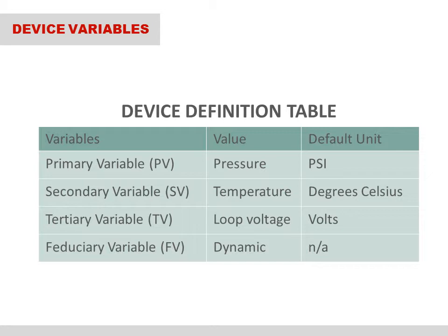The secondary variable, or SV, is the temperature in degrees Celsius. However, this is not the process temperature. This is the temperature of the 815 PT's internal electronic components. Since the 815 is a pressure transmitter, not a temperature transmitter, it is incapable of providing the temperature of the process. The SV is provided via HART. The tertiary variable, or TV, monitors or provides the loop voltage in volts. The TV is also provided via HART.